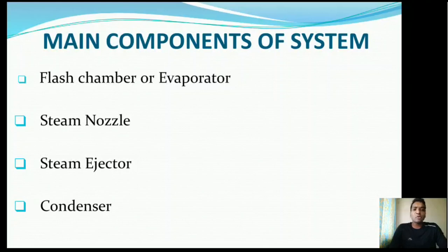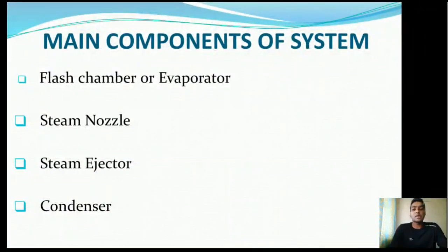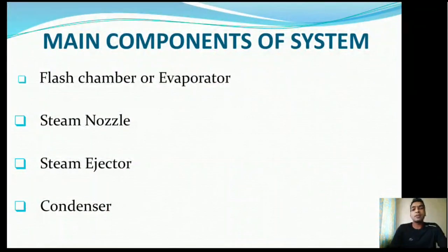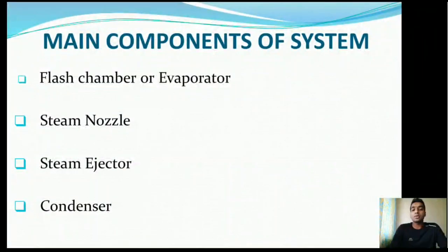The main components of the system are: flash chamber (evaporator), steam nozzle, steam ejector, and condenser. The flash chamber is a large vessel filled with the refrigerant, which is water. The steam nozzle receives high-pressure steam from the boiler and expands it, converting thermal energy into kinetic energy. The steam ejector is a pumping device that extracts gas or vapor from the system. The condenser is a shell-and-tube heat exchanger where water flows inside the tubes and refrigerant flows outside.